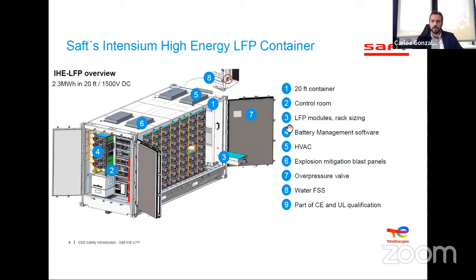Then we have the overpressure valve, number 7, which activates if there has been a thermal runaway, a fire, or an increase of temperature or release of gases inside, causing an increase of pressure inside the container. This valve releases the gases to the top part of the container, so we avoid gases reaching people nearby. Secondly, we are also reducing the pressure and temperature inside, reducing the possibility of an explosion or a bigger thermal runaway.